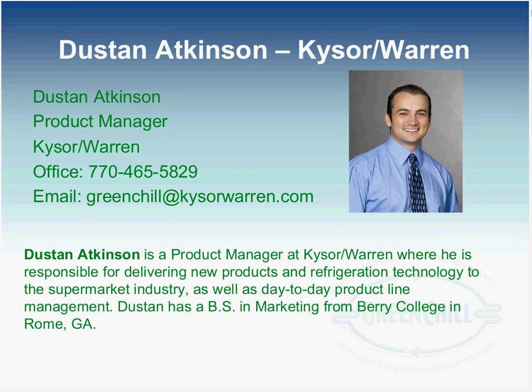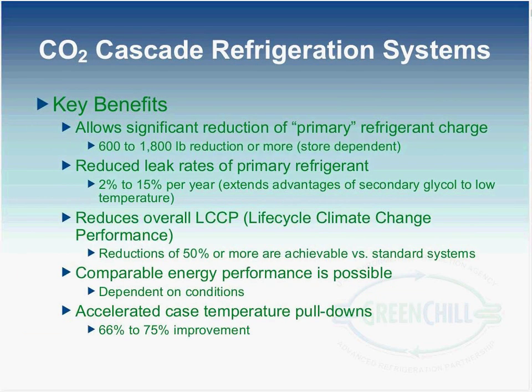Okay, thanks, Scott. Next, we're going to go to Dustan Atkinson, and he is going to present on CO2 cascade systems. Go ahead, Dustan. Thank you very much, Keely. I'm going to start by talking a little bit about the benefits of this type of system. First off, obviously, the reason we're all here is to reduce refrigerant charge and reduce our impact on the environment. This particular type of system has a pretty substantial reduction of what I'm going to call the primary refrigerant, or HFC, potentially environmentally harmful refrigerants. We see about a 600 to 1800 pound reduction, or potentially even more, depending on a specific site setup.